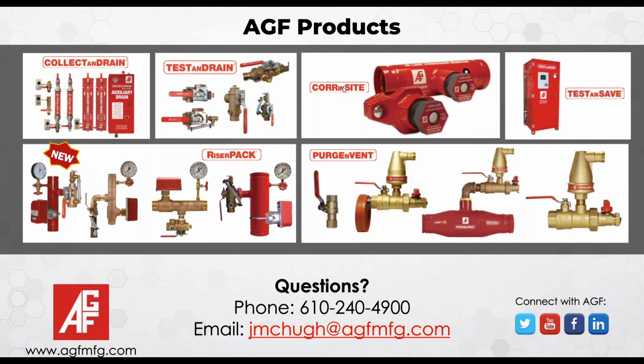And in working with steel pipe manufacturers, they said if you can address the corrosion problem in the first third of the pipe, then you can salvage that pipe. So that's why we made this the dimensions we did, to give you as early warning as possible that you are having a corrosive condition in your sprinkler pipe. You could have MIC, the microbial influenced corrosion. That could be what's causing the problem. It could be some other defect in the pipe. It could be even some other contaminant in the water is accelerating the corrosive ability in the pipe.